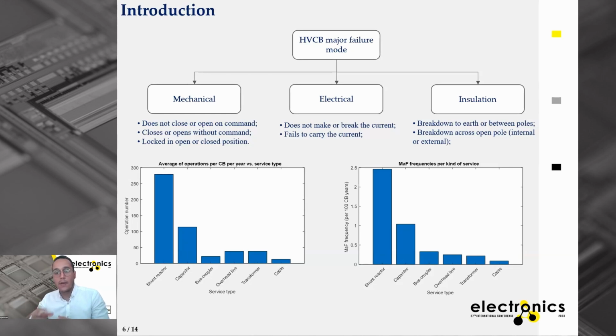So if something happens in that area, internally or across the poles, that's categorized as insulation. However, for the electrical part, the main focus is on contacts and electrical features such as resistance or misalignment of the contacts inside the circuit breaker. This is basically the division made, mainly because of SF6 gas—if there's a leakage of SF6 gas, it's also counted as insulation.